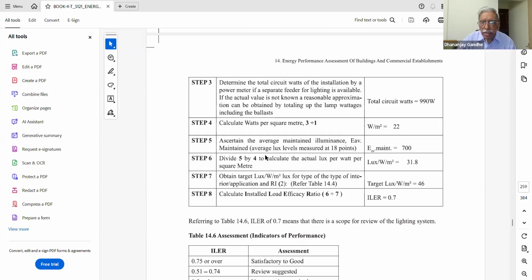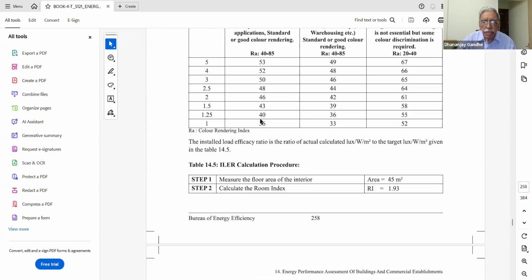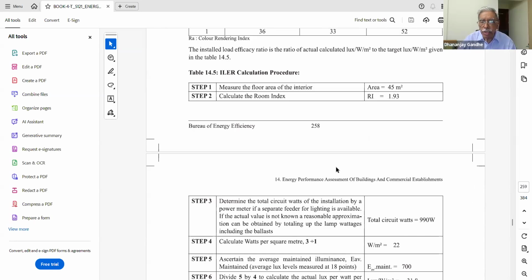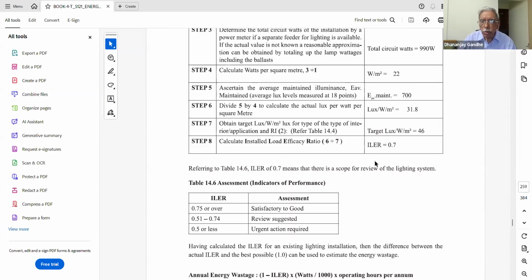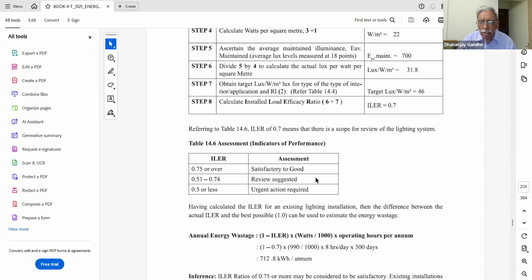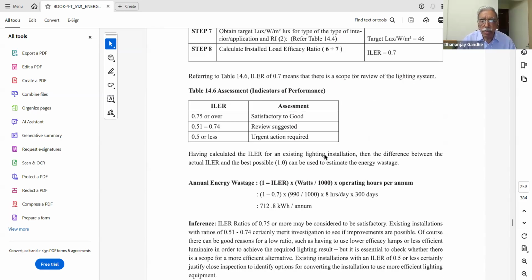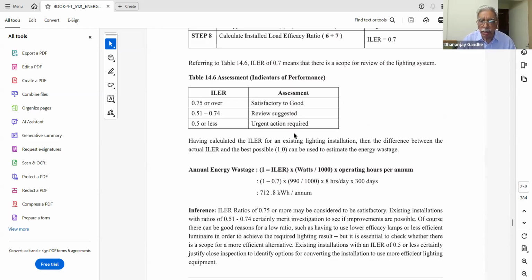As per the standard, this figure for this particular type of building should be 46. So this ratio, ILER, is 31.8 by 46. This is how the efficacy ratio for this particular area works out to about 0.7. So some review is suggested over here.